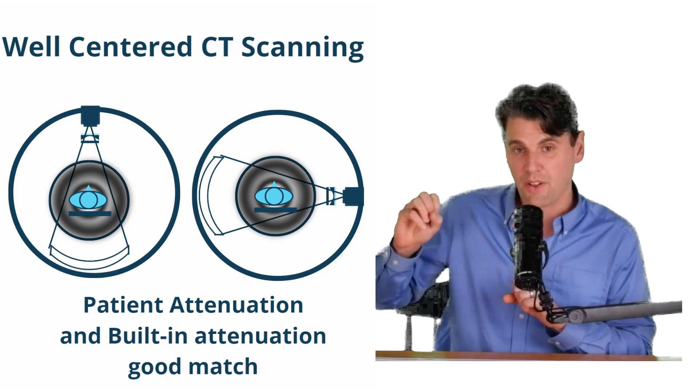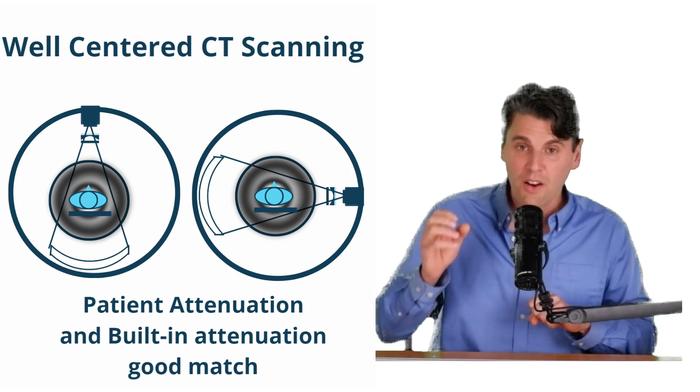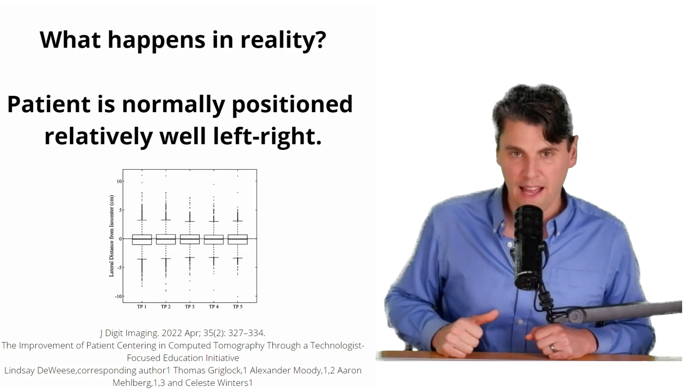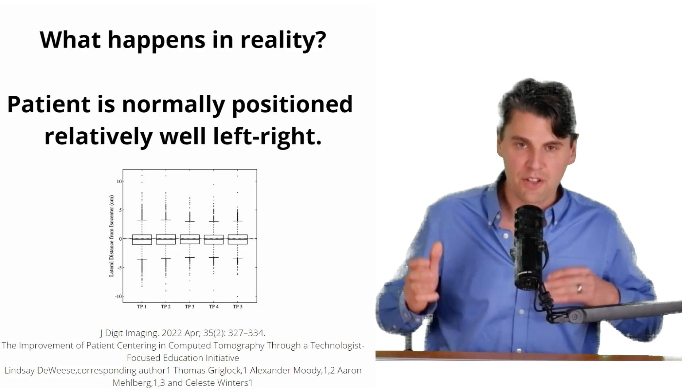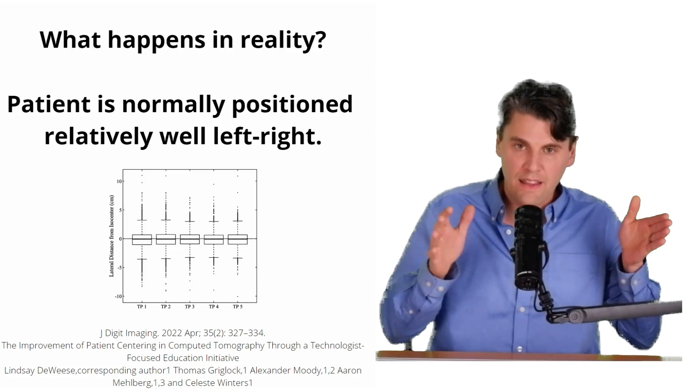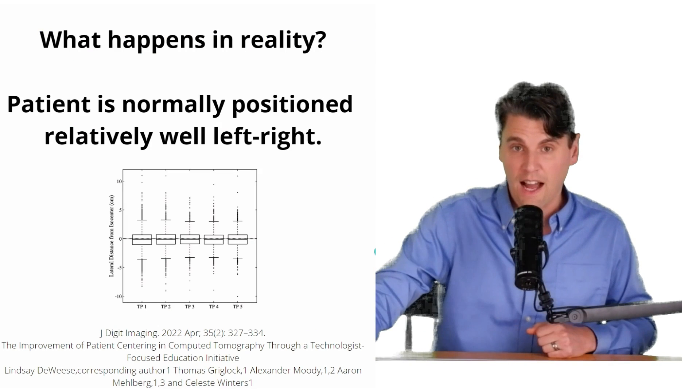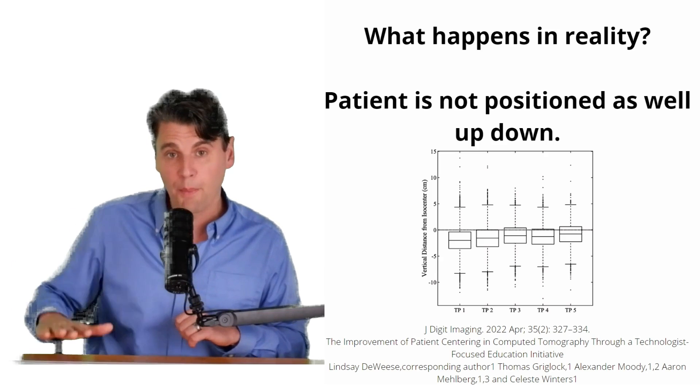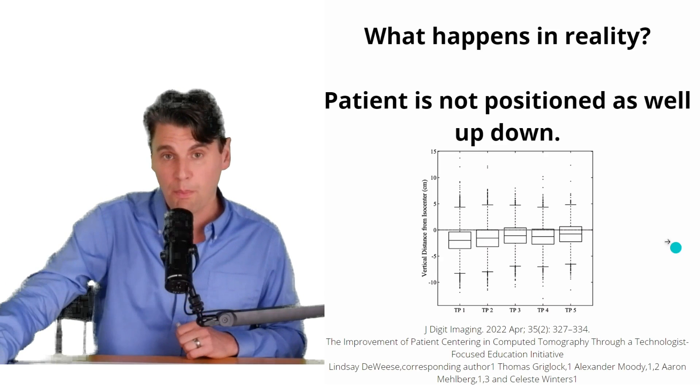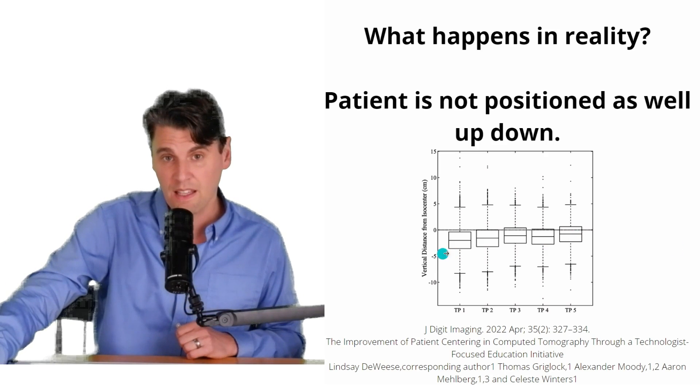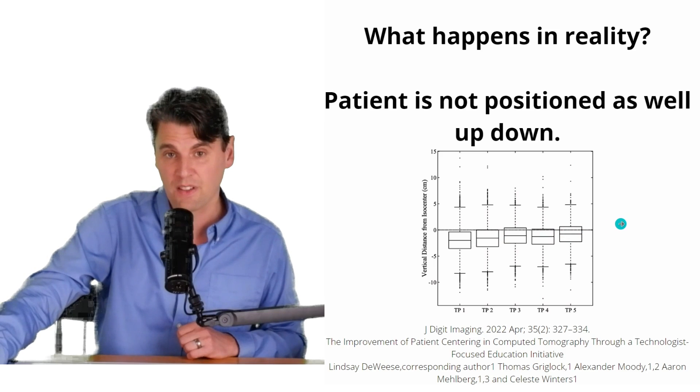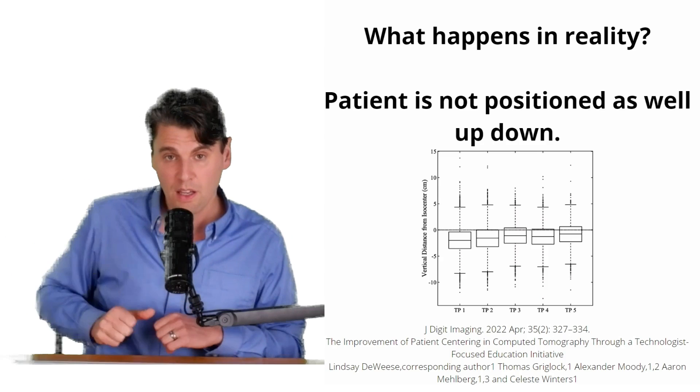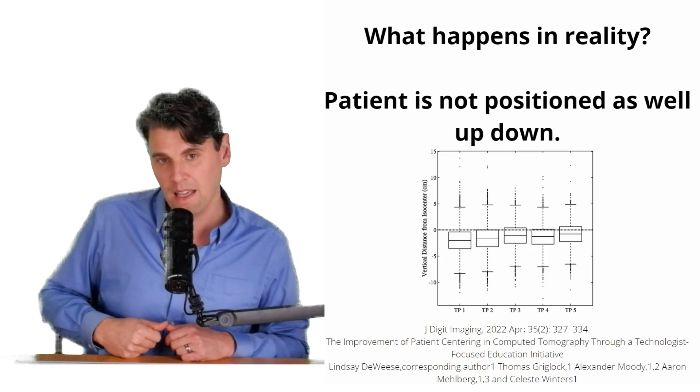But what actually happens in reality? In reality, at least on average, they're fairly well positioned in the left-right direction on the table. In addition to the variance, there's also more of a bias in the up-down direction. So more of the time, you can see the patients are usually being positioned too low in the scan field of view, such that they're not going to be optimally imaged.